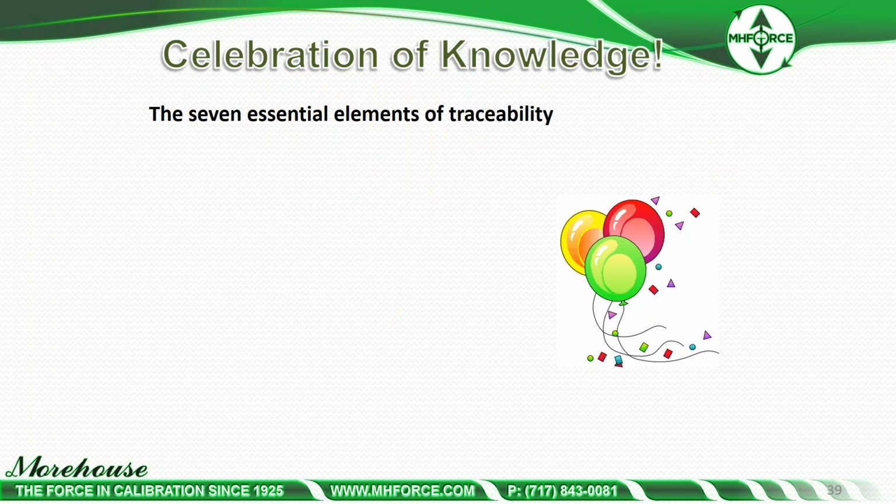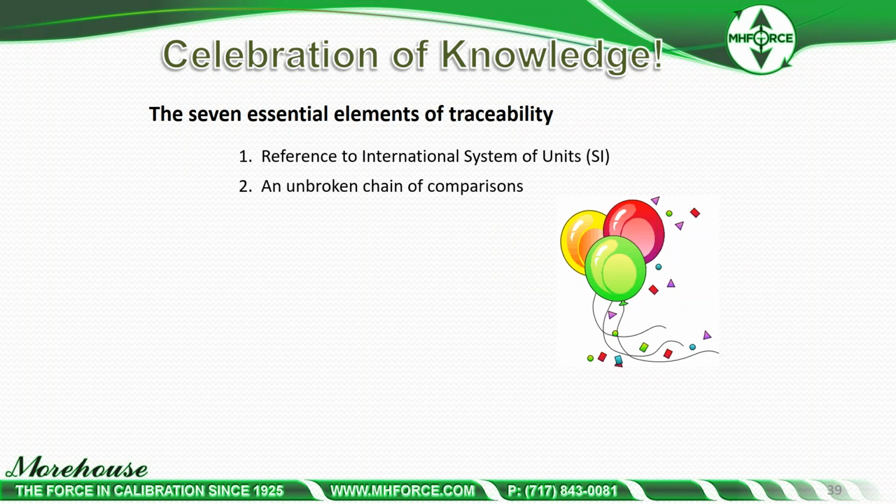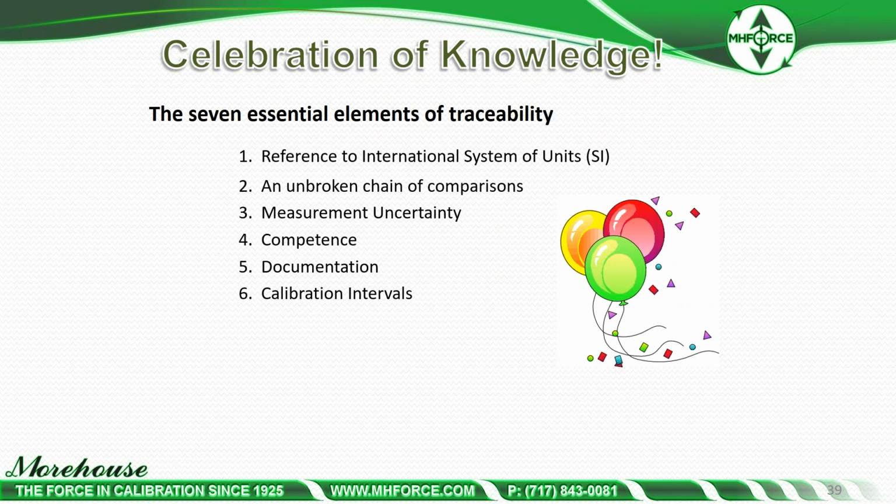Always cracks me up. So just a quick review, the 7 essential elements of traceability: reference to the International System of Units, an unbroken chain of comparisons, measurement uncertainty, competence, documentation, calibration intervals, and then what we just discussed, the measurement assurance.